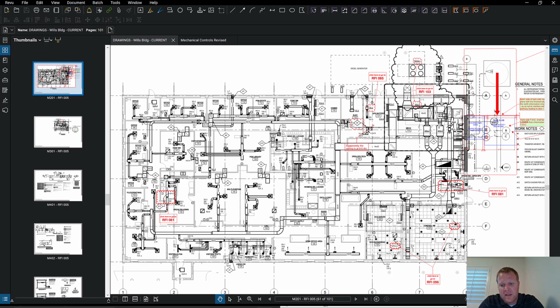What I like is getting into the project and working with the commissioning agent to work out a startup sequence, so that if the electrician is working on certain panels, we can coordinate to provide power to certain things at certain times. If that works for the electrician, we might plan to reverse the sequence in how we construct things. That means we'd try to do air handler 2 and 3 first before air handler 1, and get some of the control room stuff up and operational before we work on air handler 1 and all the ductwork and VAVs.